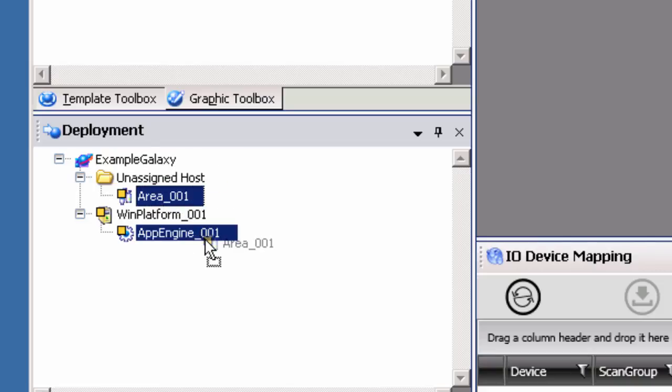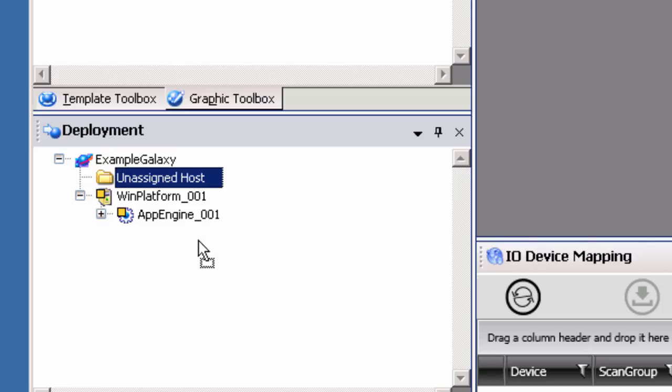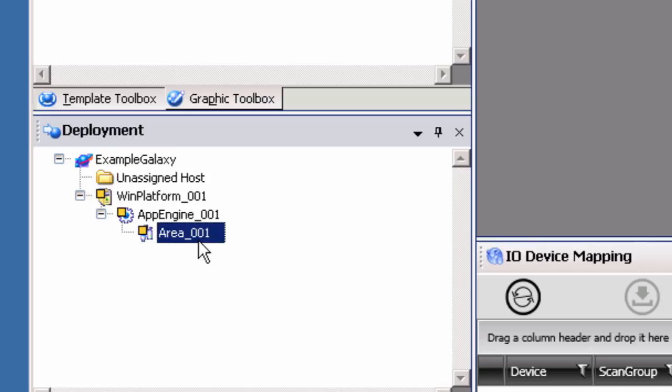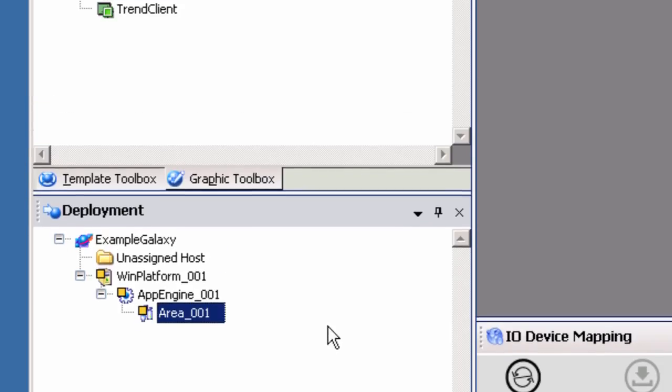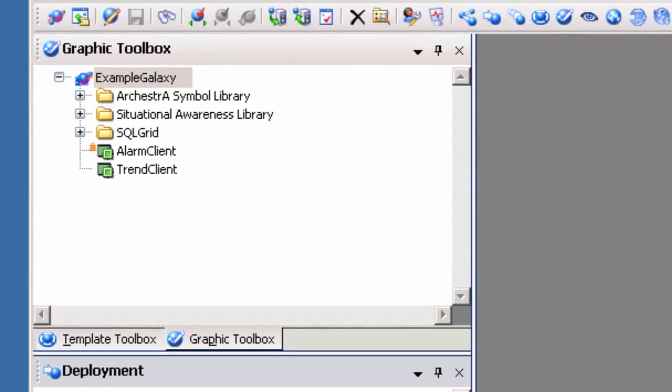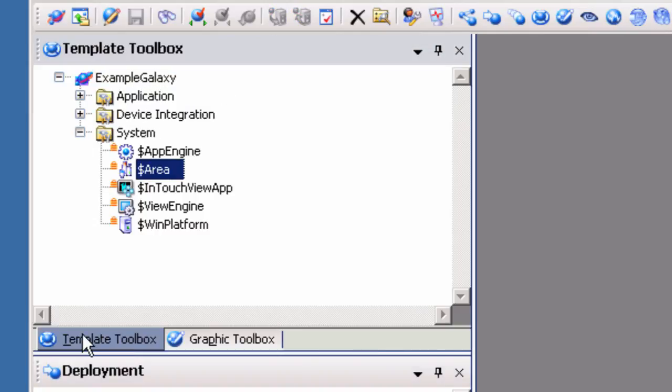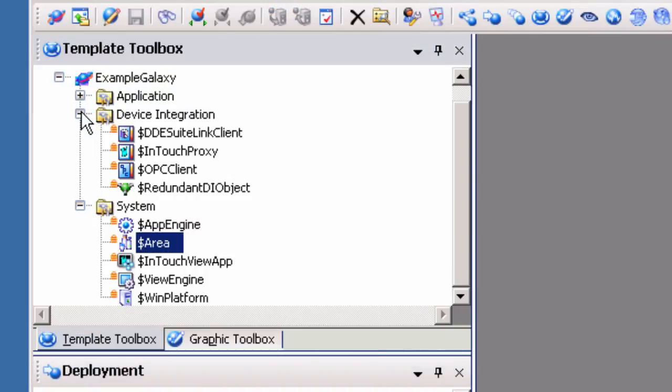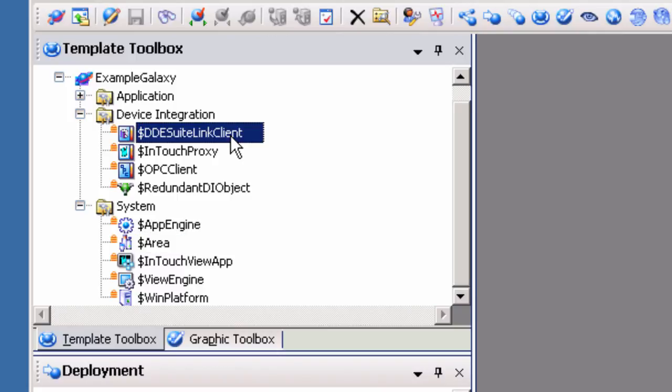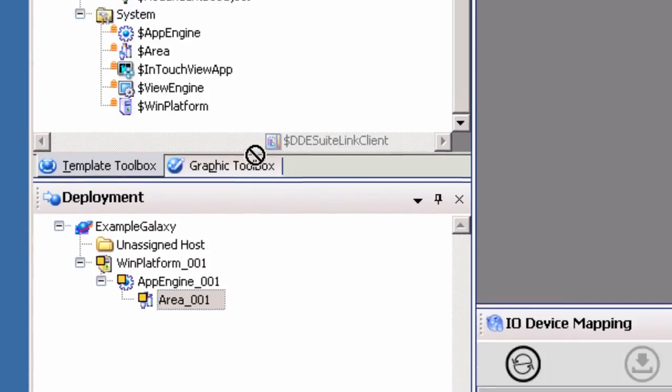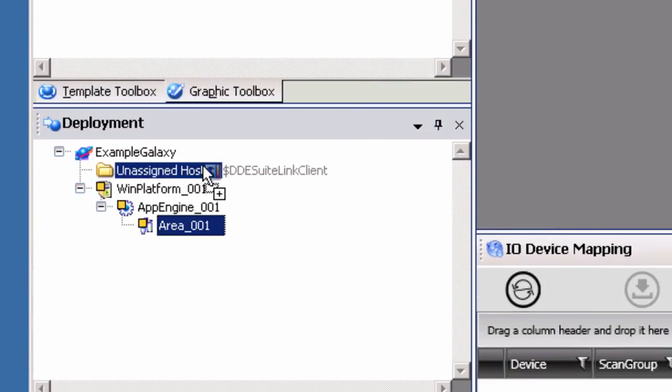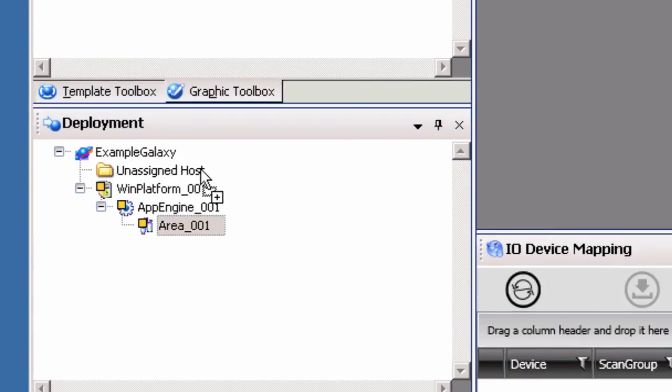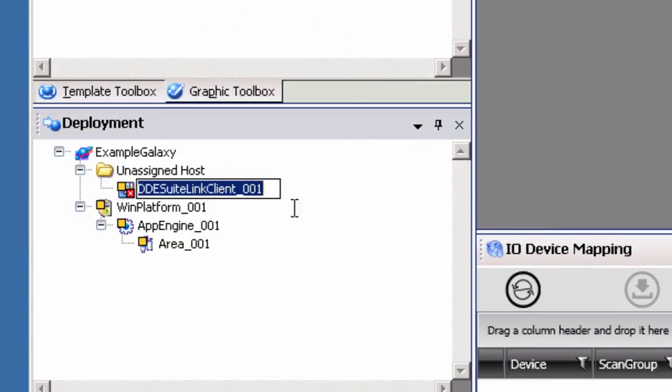Now that all of the System Objects are created and assigned, we can configure our DI Object or Device Integration Object. Begin by selecting the Template Object from the Device Integration section of the Template Toolbox. We will select the DDE SuiteLink Client Object Template because we are making a SuiteLink connection to the TopServer. Drag and drop the DDE SuiteLink Client Template Object to the Unassigned Host Folder in the Deployment View to create the DI Object.